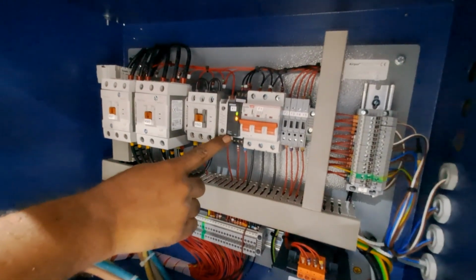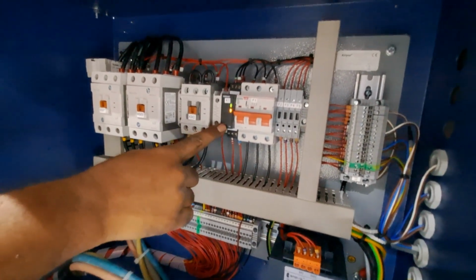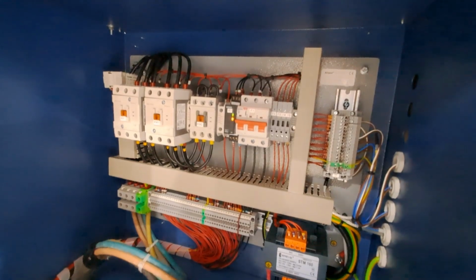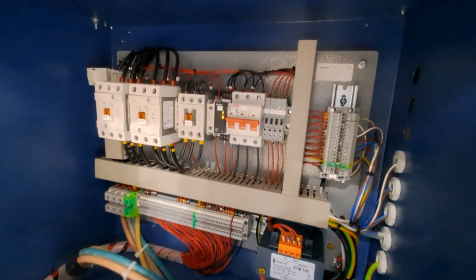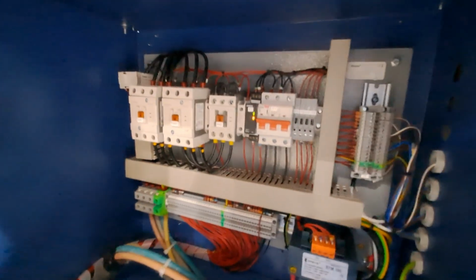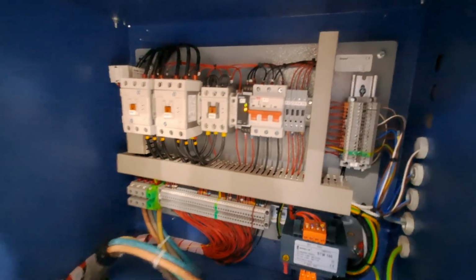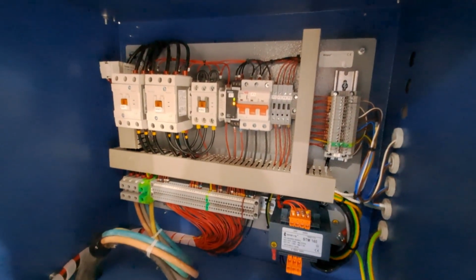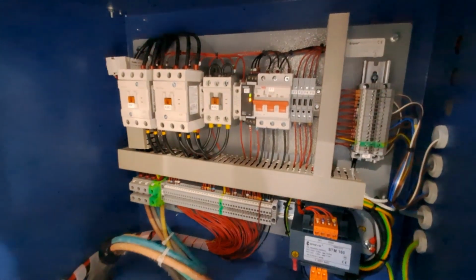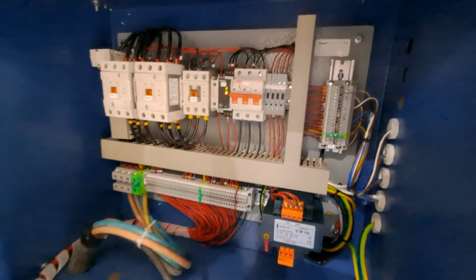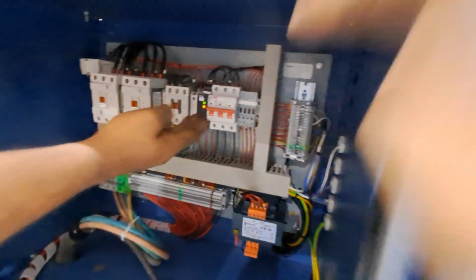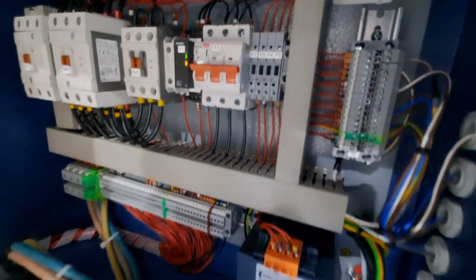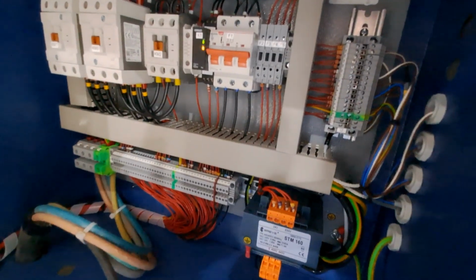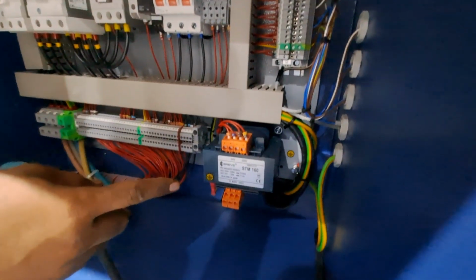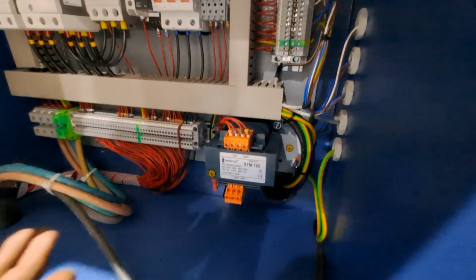We also have one phase preventer, a phase sequence relay, which, if there is any power loss, does not allow the motor to start or run. So basically it's like a phase failure. Yes, if one phase is gone, the system will turn off to prevent burning of the motor, because it is not good for the motor to run on a single phase. We have one internal MCB to switch off the main panel from inside, and we have one transformer to take an output of 24 volts to the controller.